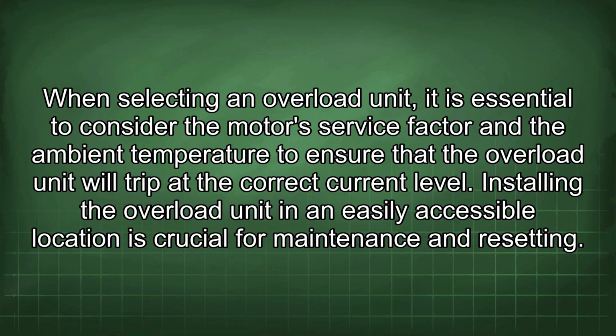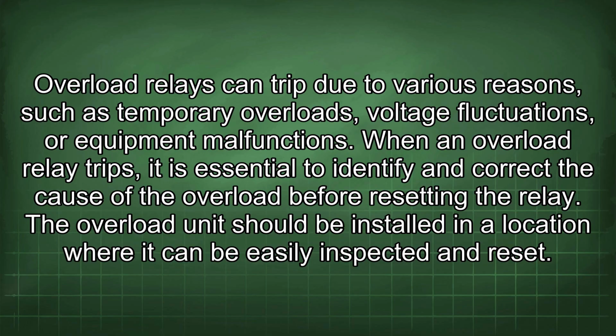Installing the overload unit in an easily accessible location is crucial for maintenance and resetting. Overload relays can trip due to various reasons, such as temporary overloads, voltage fluctuations, or equipment malfunctions. When an overload relay trips, it is essential to identify and correct the cause of the overload before resetting the relay. The overload unit should be installed in a location where it can be easily inspected and reset.